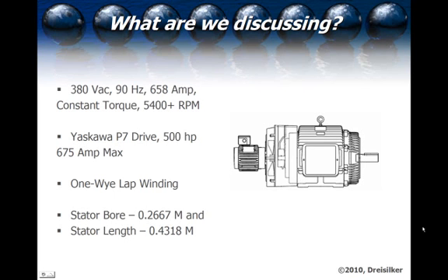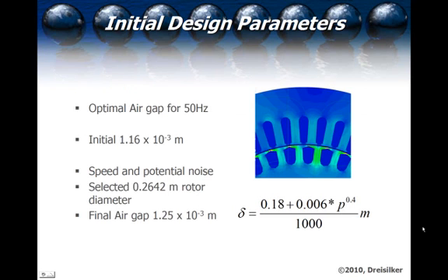This is a Dreisilker-designed machine, and in this case we were upgrading to a 60-degree C environment. The optimal air gap for this 50-hertz machine would have been 1.16 times 10 to the minus 3 meters, or about 50 thousandths on a side. The problem with that is in this type of environment, especially with the inverter, the tighter the air gap, the more potential noise you have because of permeance harmonics and magnetic waves inside the machine. At the end of this presentation, we'll show you the noise that you'll hear from the machine because of the 2-kilohertz signal used on the inverter.